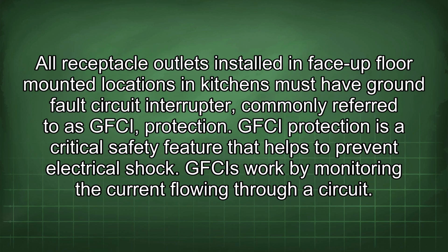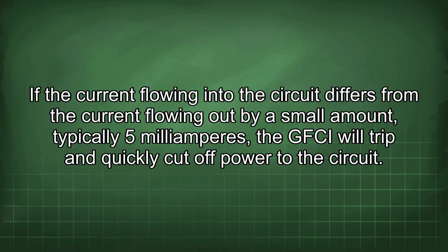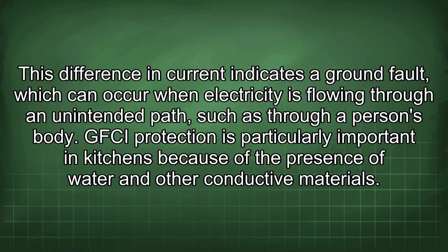All receptacle outlets installed in face-up floor-mounted locations in kitchens must have ground fault circuit interrupter, commonly referred to as GFCI, protection. GFCI protection is a critical safety feature that helps to prevent electrical shock. GFCIs work by monitoring the current flowing through a circuit. If the current flowing into the circuit differs from the current flowing out by a small amount, typically 5 mA, the GFCI will trip and quickly cut off power to the circuit. This difference in current indicates a ground fault, which can occur when electricity is flowing through an unintended path, such as through a person's body.